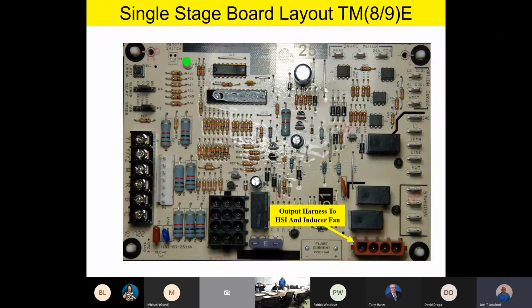Okay, as we move around towards the bottom of the board, we see that we have an output harness to our hot surface igniter and our inducer fan motor. We'll harness in right here, and it's just a little 4-pin harness. That's going to be 120 volt output to the hot surface igniter and our inducer fan motor.